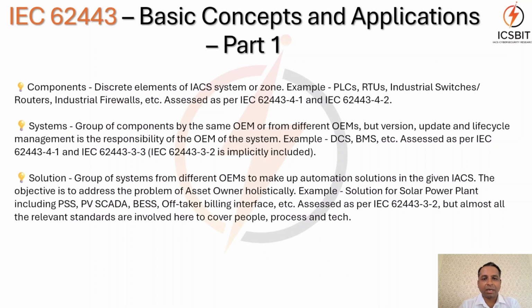This is why I mentioned it becomes complex, because when we are assessing these systems, we carry out risk assessment as per 62443-3-2. That's why I mentioned it as implicitly included. We also formulate zones and conduits within the system. Please note, it is not a site, it is a system, still in the lab of the OEM. So we formulate those zones and conduits.